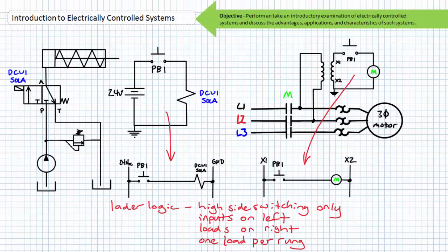This ensures that overcurrent protection devices like fuses and circuit breakers function as intended and ensures that an errant connection to ground does not inadvertently start an actuator. The one exception to this rule are the normally closed contacts associated with a motor starter, which we'll discuss later.